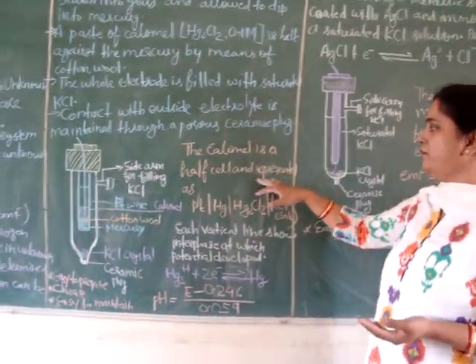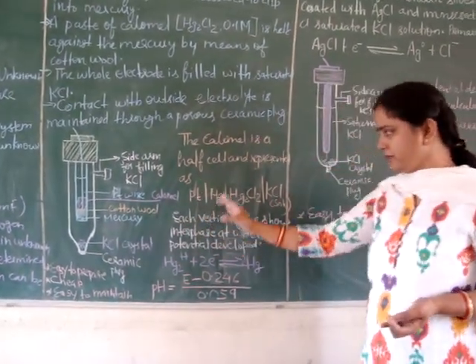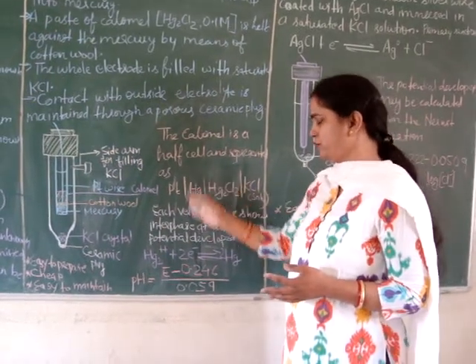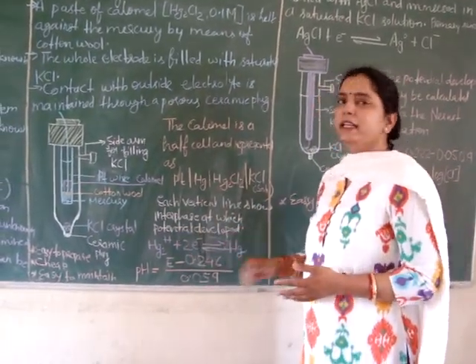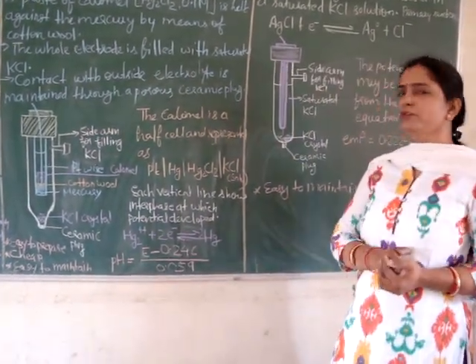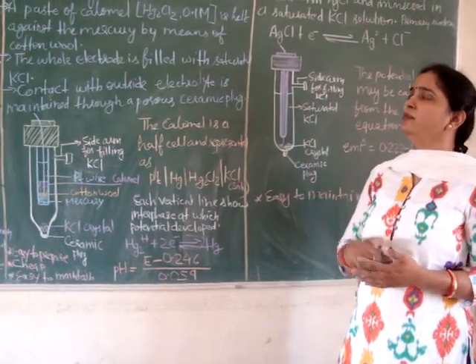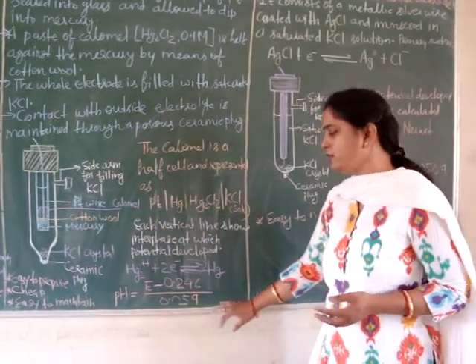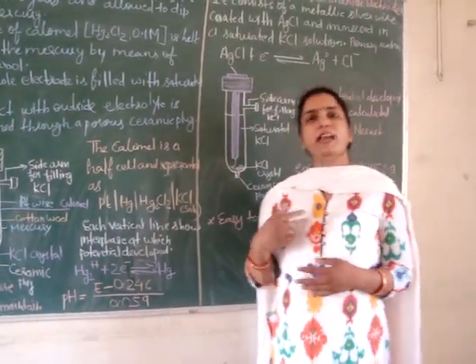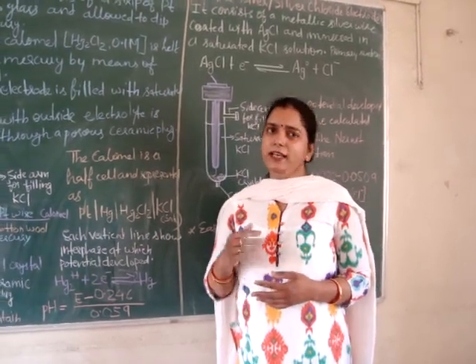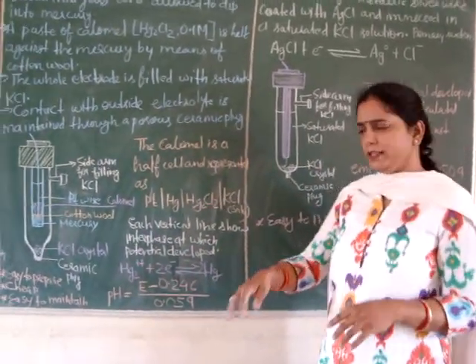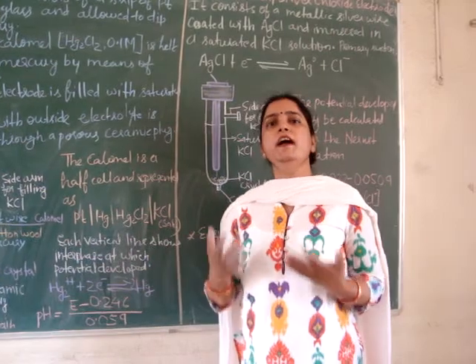The calomel electrode is a half cell and it is represented as: platinum | mercury | mercury chloride | potassium chloride solution (saturated). Each vertical line shows an interface, and at this interface the potential is generated. The primary reaction responsible for the potential difference is mercury ions accepting electrons and being converted into mercury. We can calculate the pH with the help of the calomel reference electrode using this formula: pH = (E − 0.246) / 0.059, where 0.246 is the potential difference of the calomel electrode calculated with respect to the hydrogen electrode.